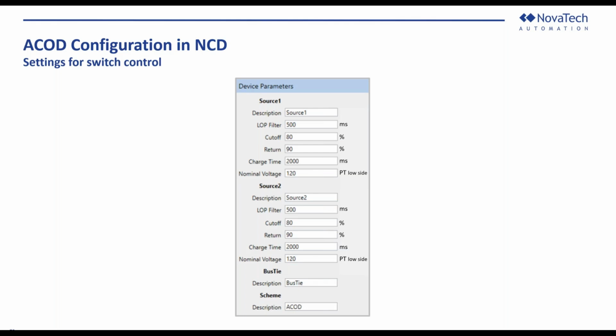This is looking at the actual switch that's doing the operating here for source 1. You're giving it a time window to operate. If this is a slower switch, maybe you need to give it a little bit more time for ACOD to be able to recognize that it's changed positions from open to close or close to open. This is where that switch failure also comes into play. We have the same settings for source 2, so that way you can configure each switch independently of each other in case they are different hardware and they have different specifications you need to follow.